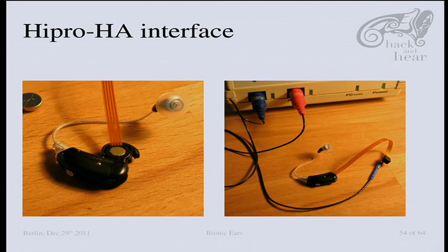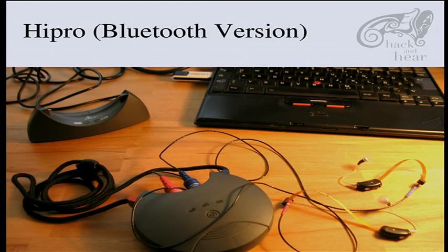The Hipro is the same for nearly all hearing aid brands, so you can use it for Siemens and Phonak and whatever. But these small flat cables are different for nearly every hearing aid. So if you try to buy this Hipro on the black market, you also have to buy those cables. There's also a Bluetooth version that also ended up in my hands.